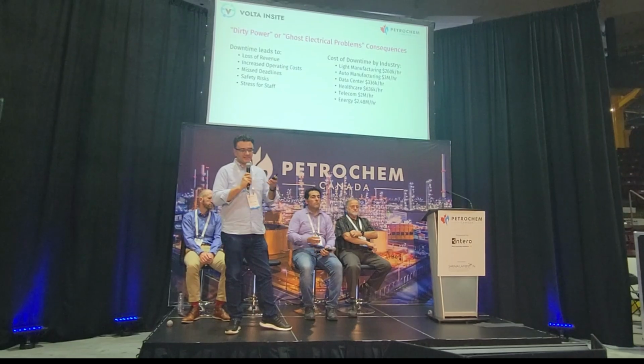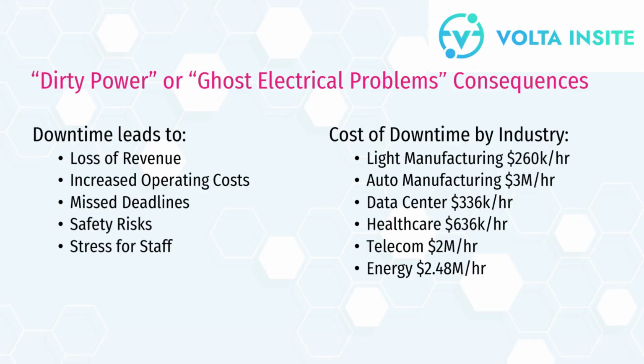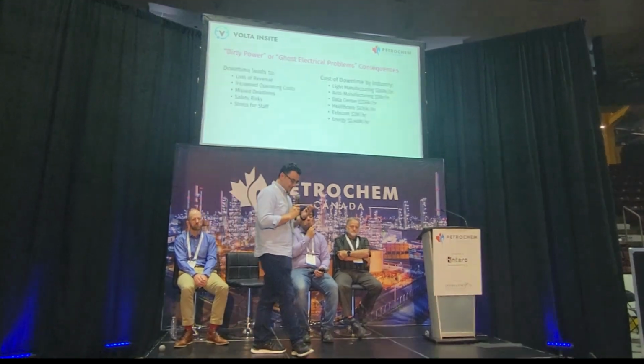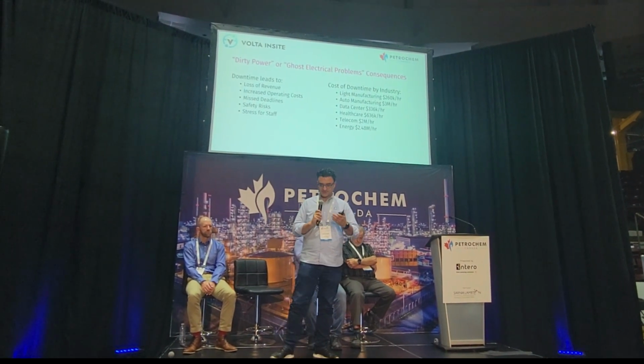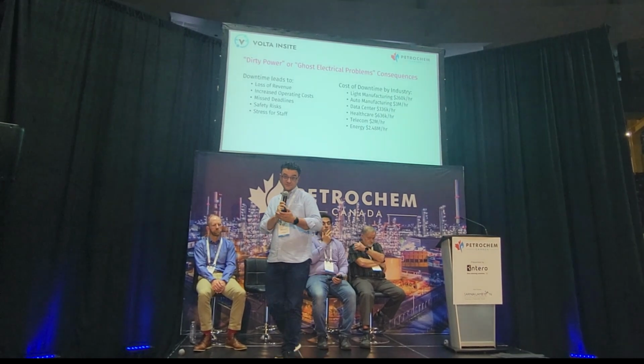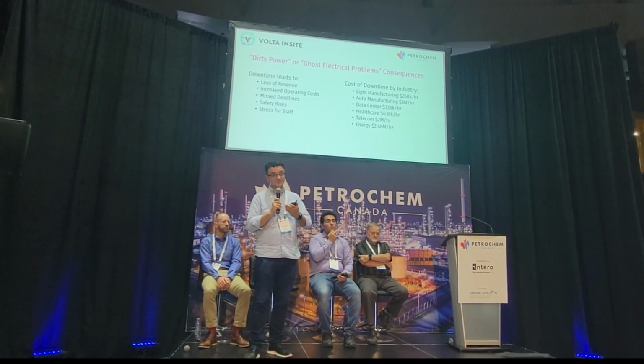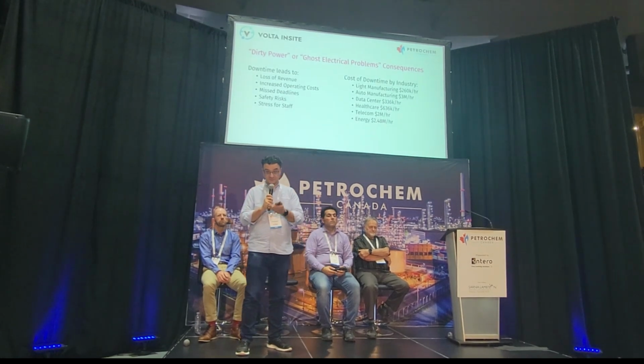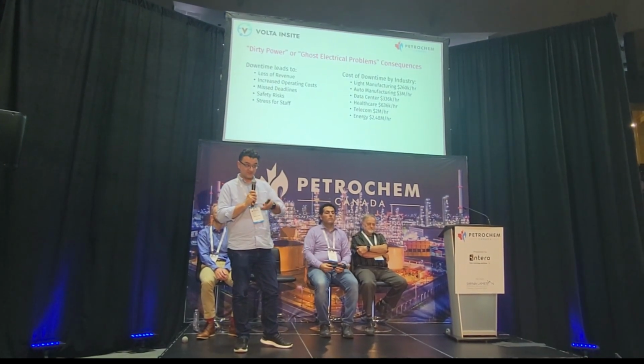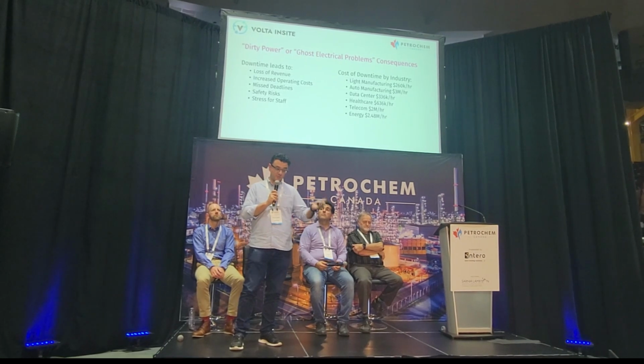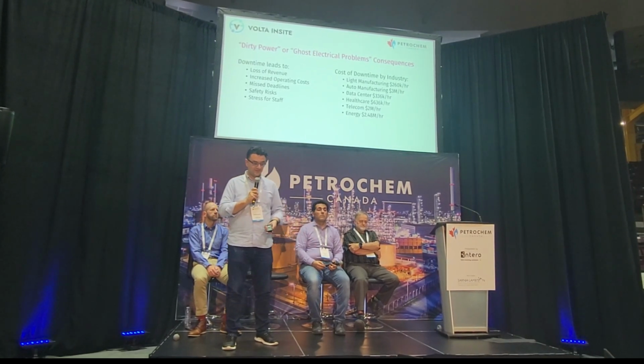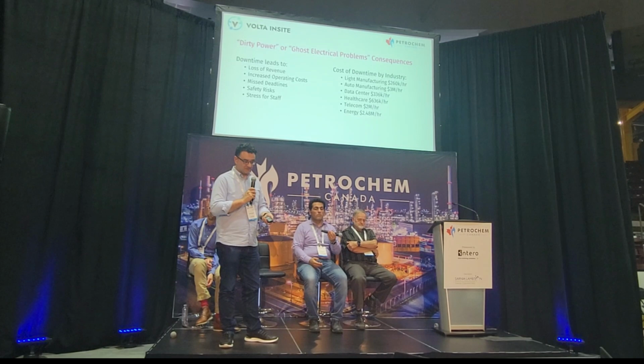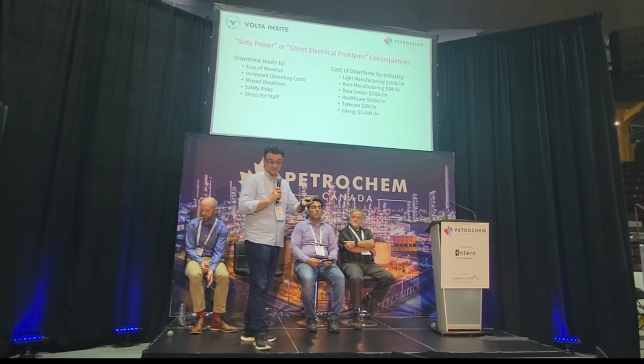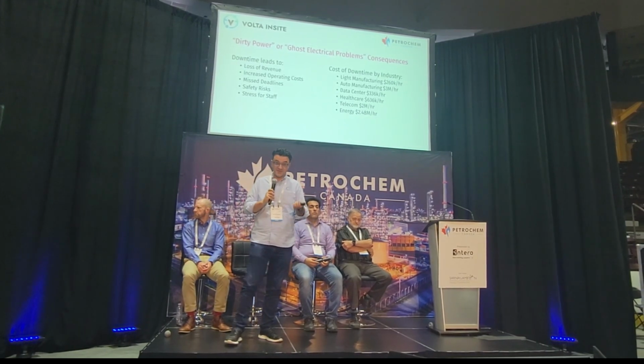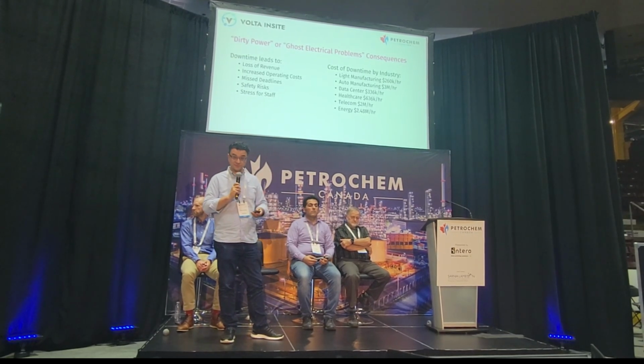So why is it important to maintain good power quality and eliminate ghost electrical problems? Because if those create catastrophic events in terms of your equipment, it's not necessarily even the cost of the equipment that's expensive to replace, it's the downtime associated with the lost equipment that's more expensive. So on this page, we talk about light manufacturing, $200,000 an hour, up to energy producers, maybe $2 million an hour. And that's what we're trying to eliminate.